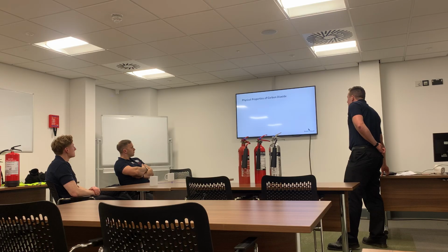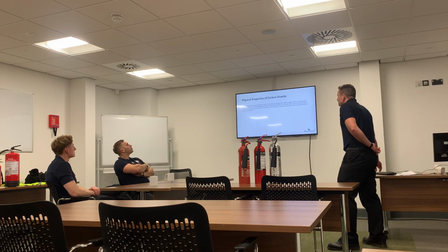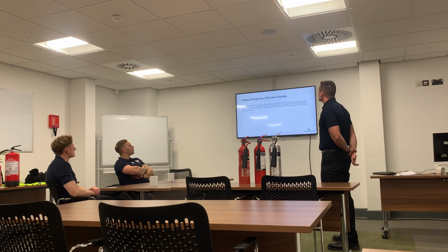So, the physical properties of carbon dioxide. Carbon dioxide has several properties which make it an acceptable firefighting agent. It does not react with most substances, with the metal magnesium being a notable exception. It is stored under pressure and therefore provides its own pressure for discharge. On discharge, it is in a gaseous state and is therefore able to penetrate to all parts of the fire area.